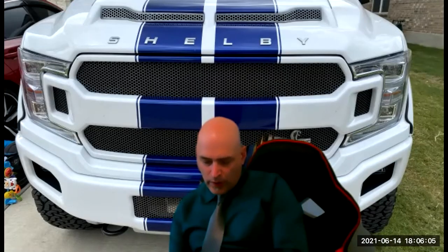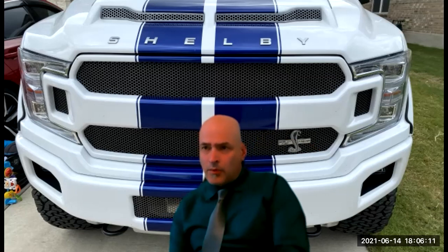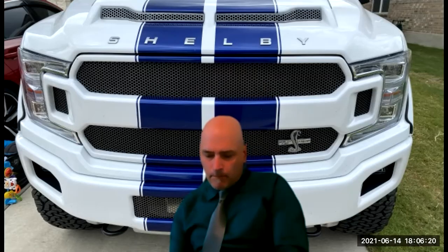Going over what you did, the example you gave me were the two that you mentioned, the 3,200 square foot home, and they gave the cooking appliance, and you said something else. I didn't catch that second part they gave you. I think they said, assume an 8,000 watt dryer and two 3,500 watt cooking appliances, and a 6,000 watt wall mounted oven or something to that effect. So it had a few.